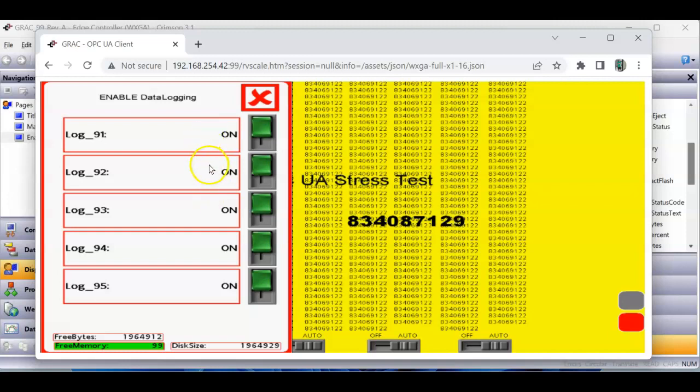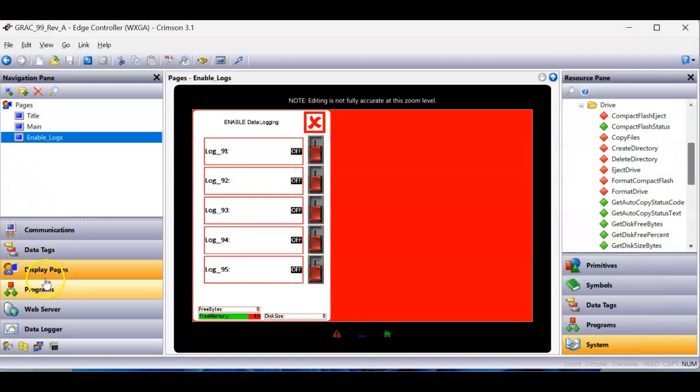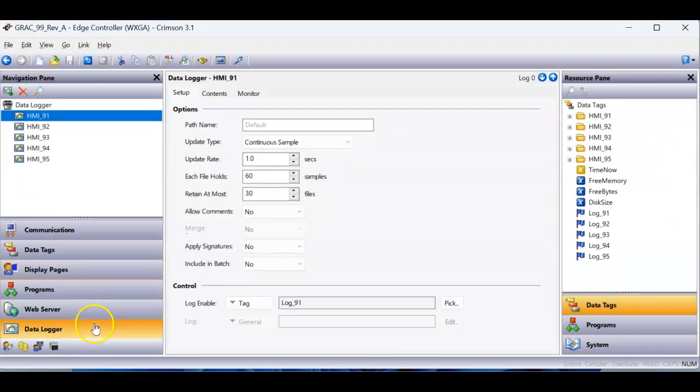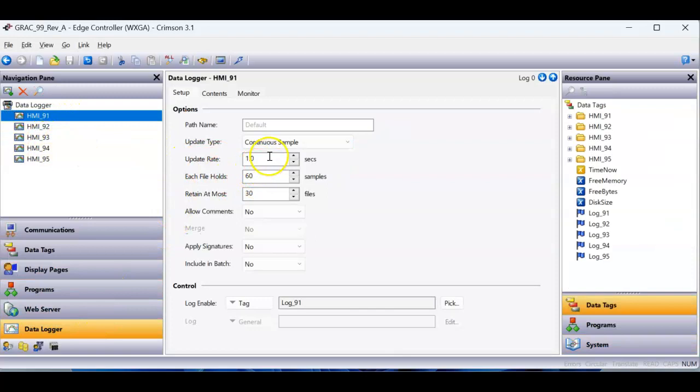So, each one of these is actually logging 1,000 tags. Let me show you in the Crimson database. I'll go over here, go to my data logger right here. You can see each one of these is my data logs. Once a second, continuous sample. Each file holds 60 samples, 30 files at most.